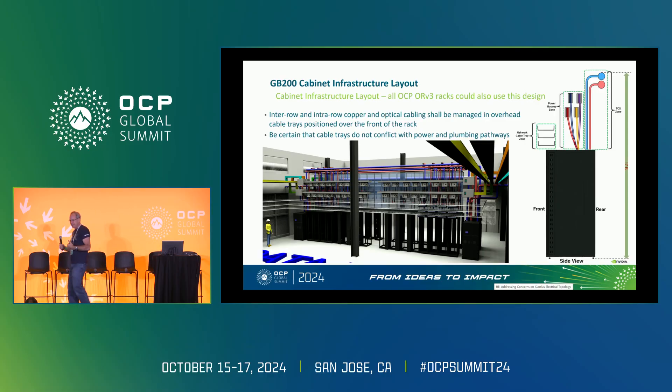Physical modeling — we love doing the physical modeling. We've got our Omniverse digital twins. It shows the patch panels, the drop boxes, breaker access, energy valves for the water overhead. This shows an overhead configuration in a data center that had 17 feet of clearance. Could you do it in 15 feet? Could you put the water under the floor? Yes. But you've got to model it, because you're talking about eight power drops in every rack.